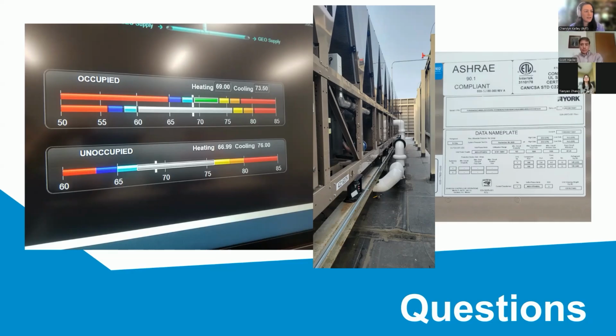David asked for more detail on the impact of setbacks on efficiency, and whether the team verified how long it took buildings to reach required temperatures. We did not look at that impact; we just documented what we saw at the time of the site visit. We believe that if buildings implemented optimal start programming, it could automatically bring temperatures back to set points before occupancy and help alleviate those issues, but we did not test or verify how early setbacks need to start for the building to bounce back.